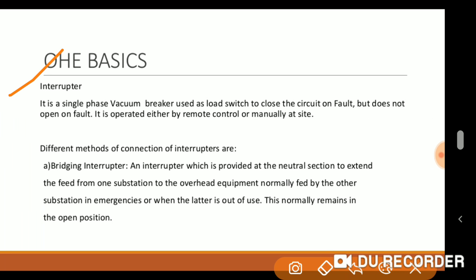Interrupter. It is a single phase vacuum breaker used as load switch to close the circuit on fault but does not open on fault. It is operated either by remote control or manually at site. Different methods of connection of interrupters are bridging interrupters. An interrupter which is provided at the neutral section to extend the feed from one substation to the overhead equipment normally fed by the other substation in emergencies.